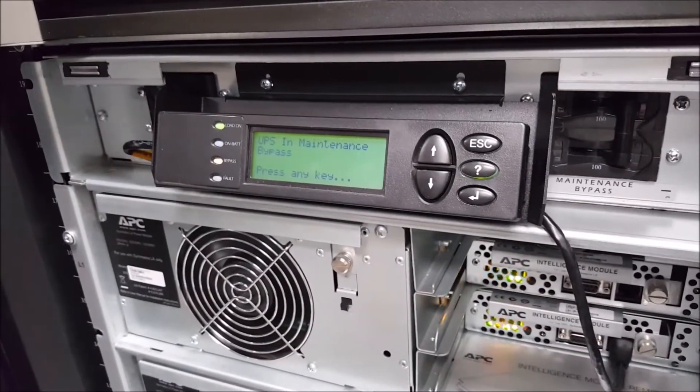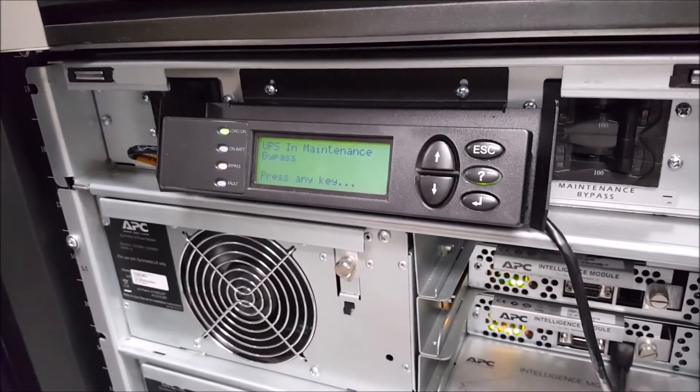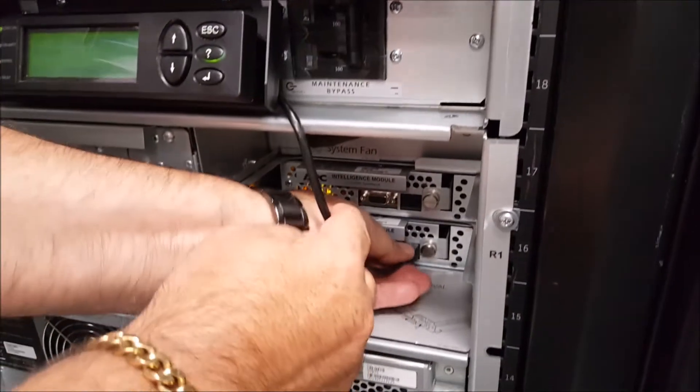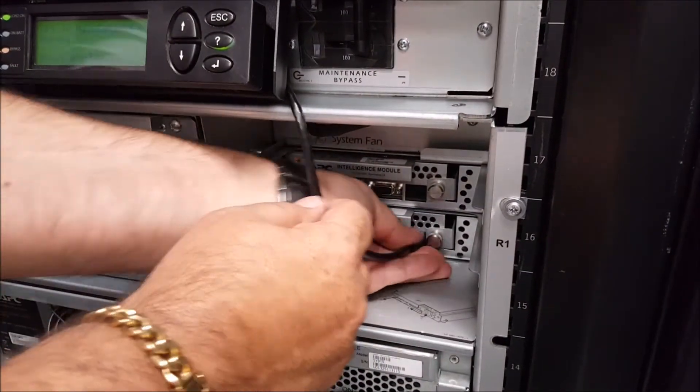After the UPS is safely in maintenance bypass, you'll want to remove the ethernet cable that connects the display to the intelligence modules.